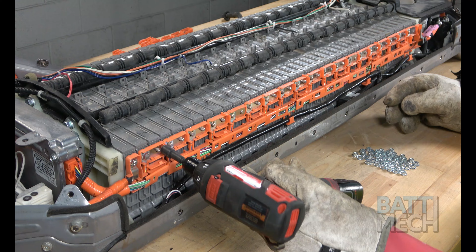Once all the bus bars are replaced, attach the wiring harness to the battery modules using BattMech supplied nuts. Pay close attention to the first and last terminals on this battery pack. Make sure the main wire eyelet is installed into the wiring harness on this side before putting the new nuts on the first and last terminals. As you can see, this wire can become dislodged very easily.